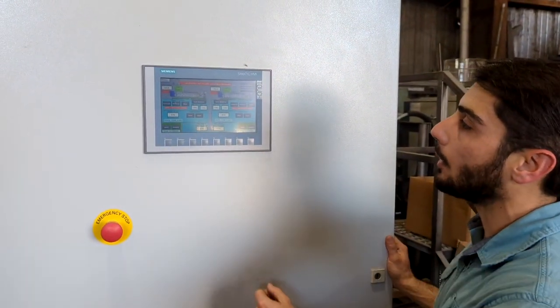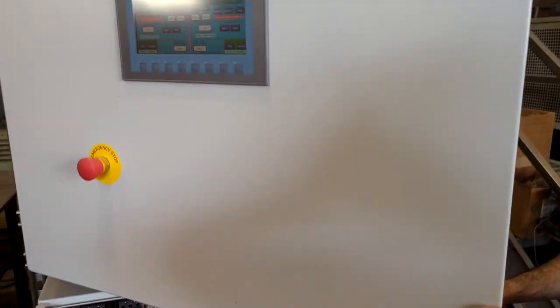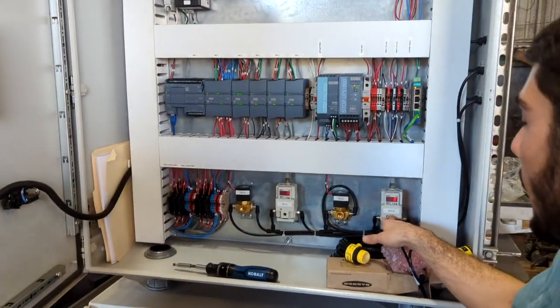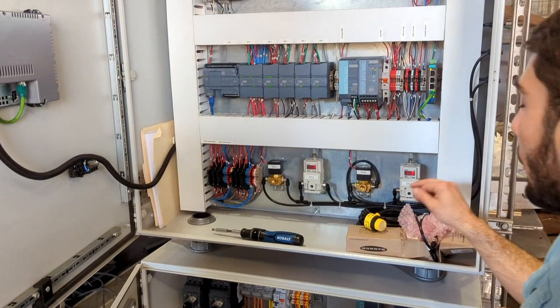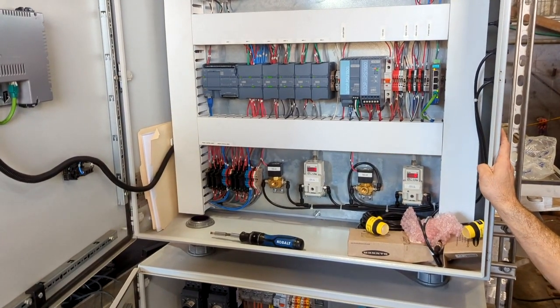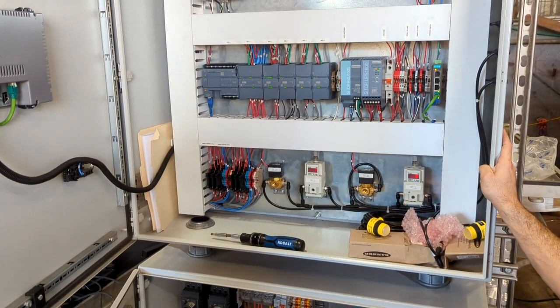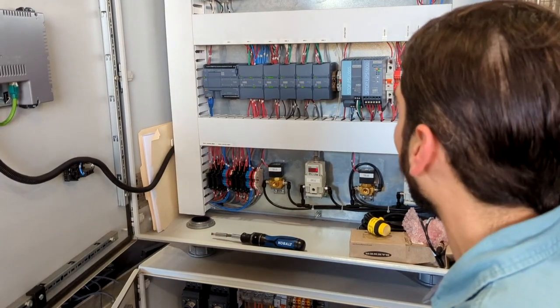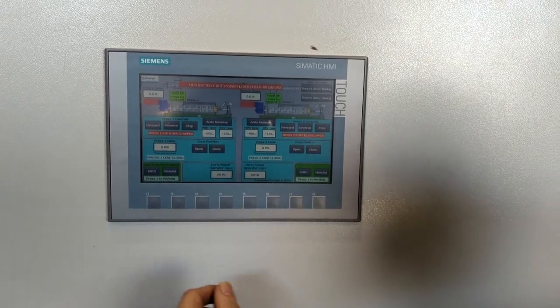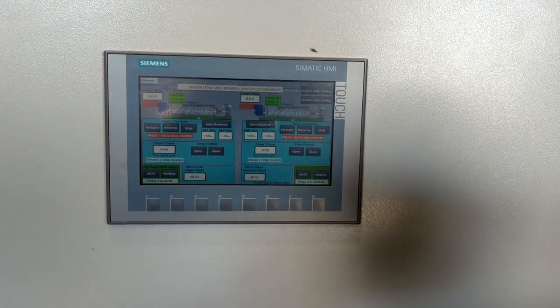We have some feedback that is provided by these two instruments here, two I to P transducers that we're using to control the cone and let us know how much pressure we actually have at the unit itself in the field. Going back to the screen now, we have our level sensor options. There's a manual and an auto you can run it in. We're showing it in manual right now. Let's go ahead and switch that over to auto.